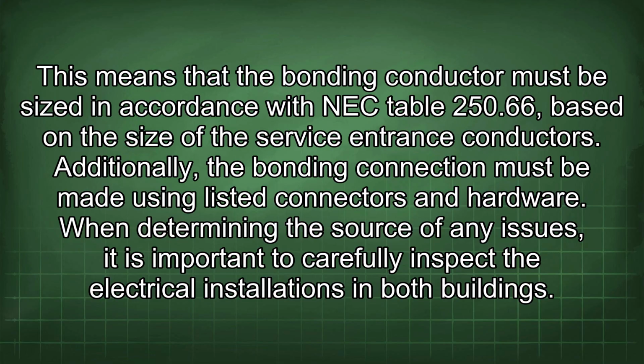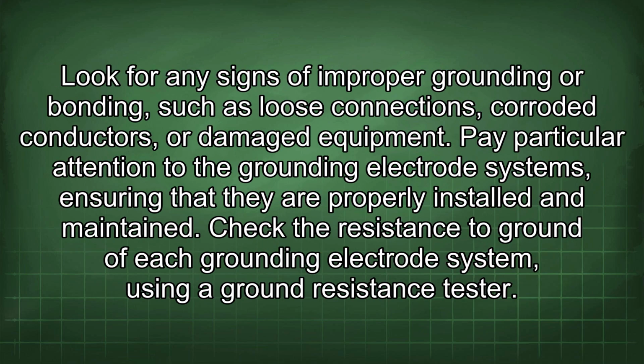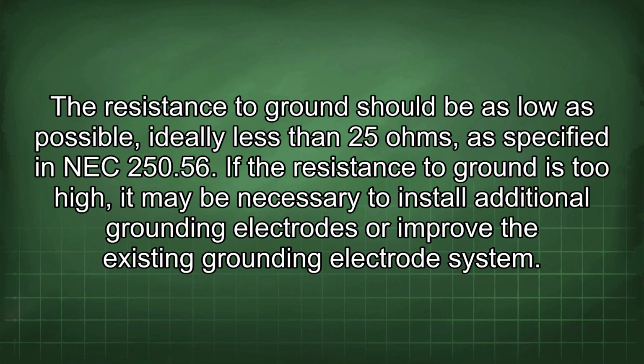When determining the source of any issues, it is important to carefully inspect the electrical installations in both buildings. Look for any signs of improper grounding or bonding, such as loose connections, corroded conductors, or damaged equipment. Pay particular attention to the grounding electrode systems, ensuring that they are properly installed and maintained. Check the resistance to ground of each grounding electrode system using a ground resistance tester. The resistance to ground should be as low as possible, ideally less than 25 ohms, as specified in NEC 250.56. If the resistance to ground is too high, it may be necessary to install additional grounding electrodes or improve the existing grounding electrode system.